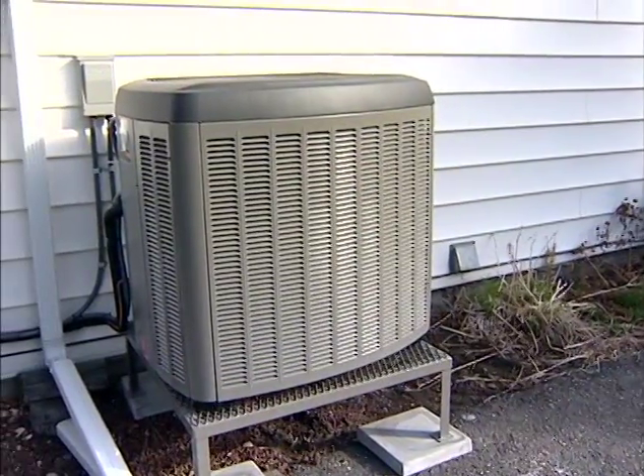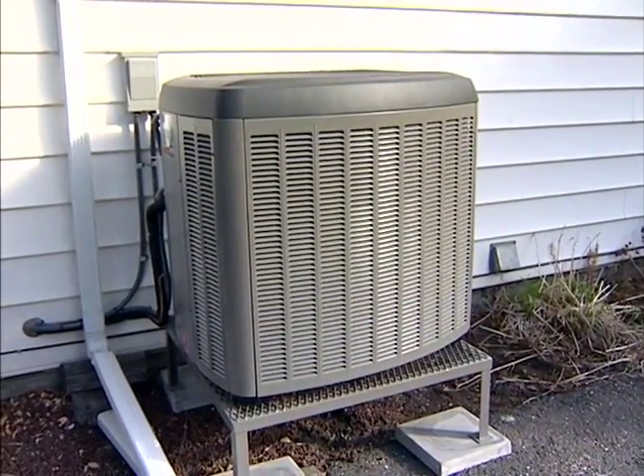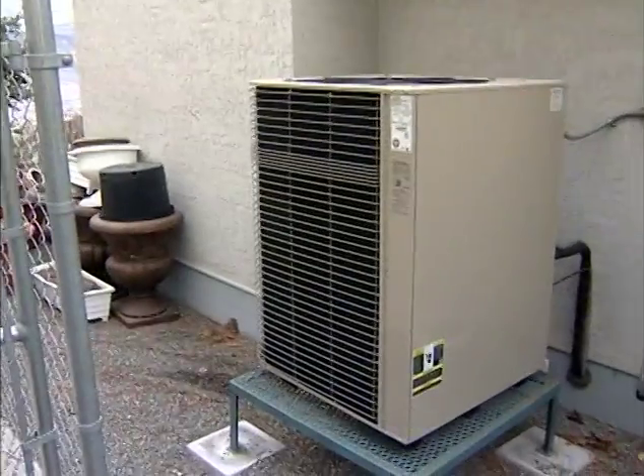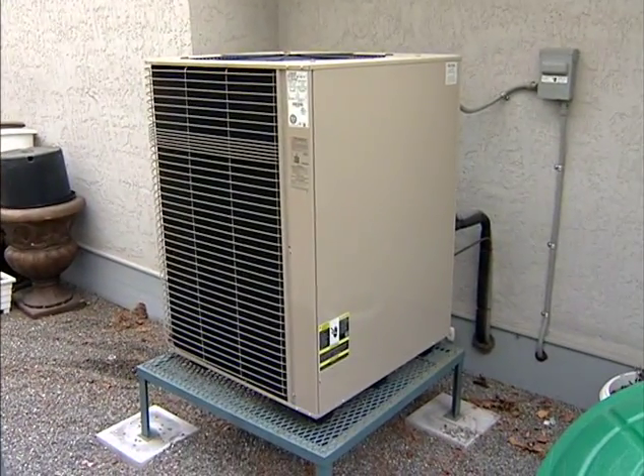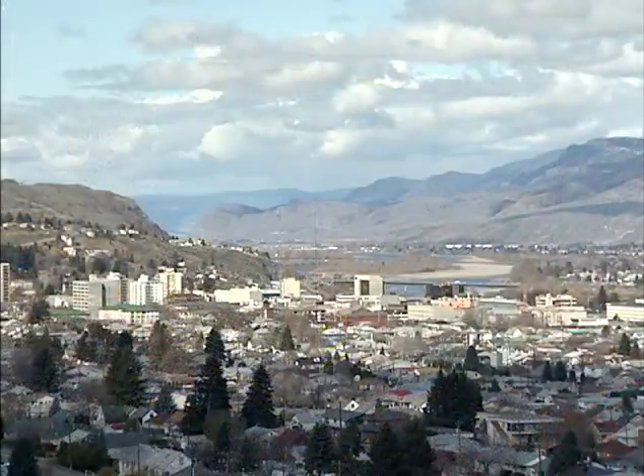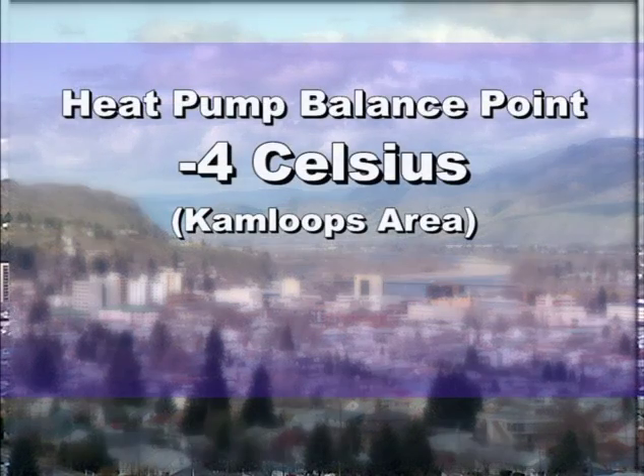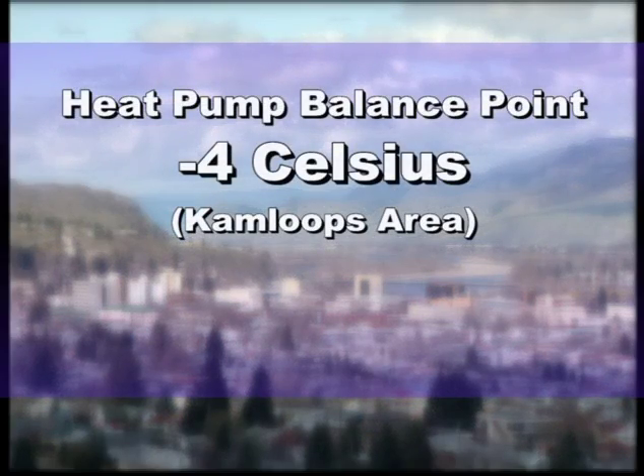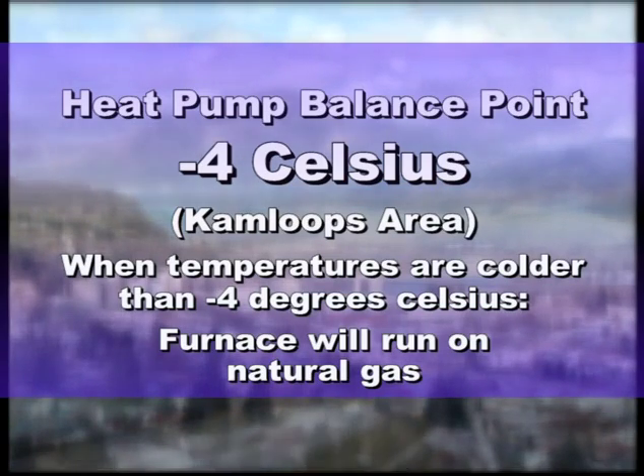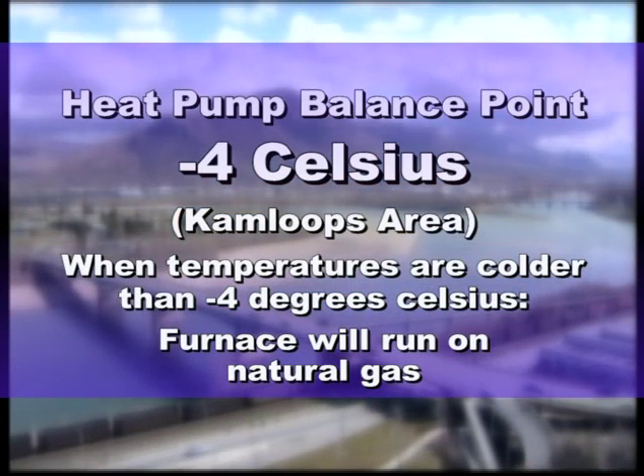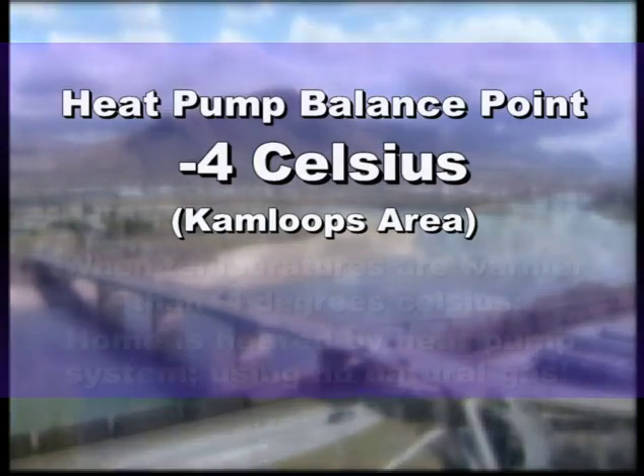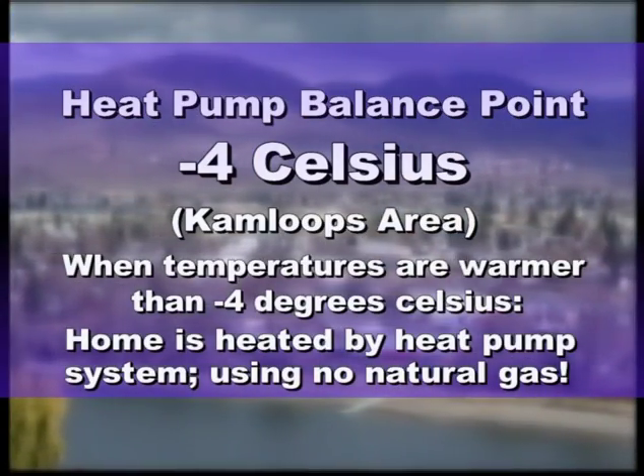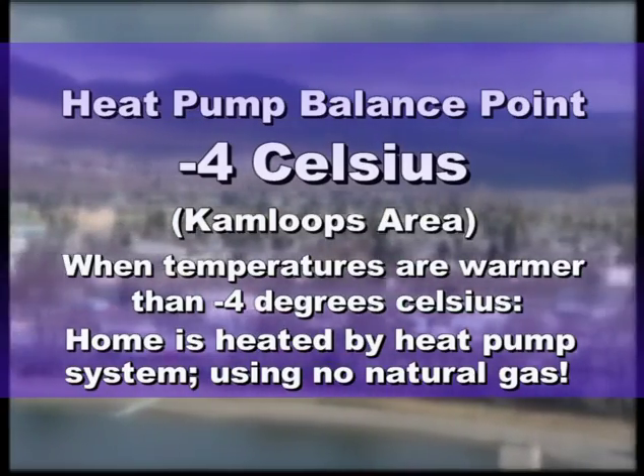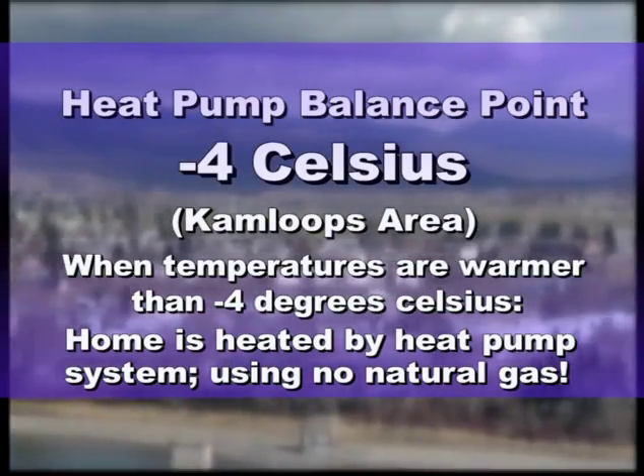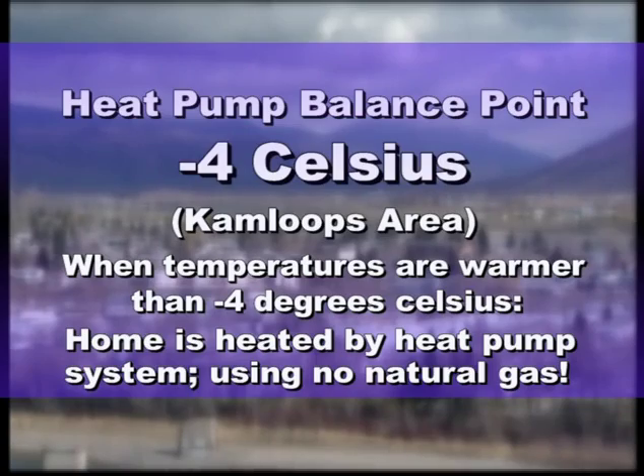Now, even though a heat pump system can absorb heat from very low temperatures, there is a limit as to how cold it can be and still work efficiently. In the Kamloops area, that balance point is minus 4 degrees. In other words, when outside temperatures are colder than minus 4 degrees, the furnace will run on natural gas. But when temperatures are minus 4 and warmer, the home is heated by the heat pump system the majority of the time using no natural gas.